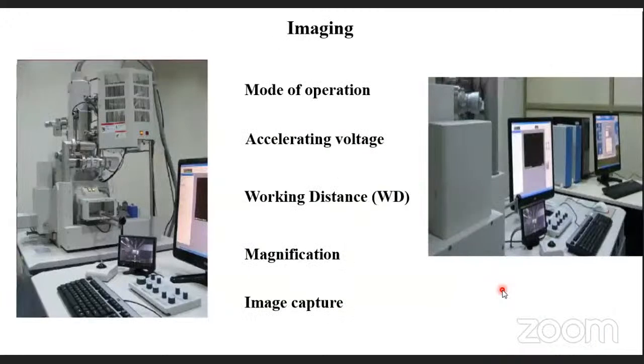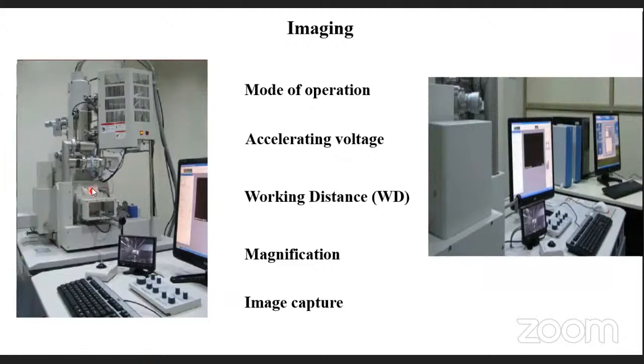After sample preparation, we come to the instrument and open the exchange chamber. We place the sample holder inside, push the sample in, close the chamber, and start the analysis. Before going for analysis, you should understand which mode you require — decided by you and the technical staff. We have different modes: secondary electron mode for basic analysis, and backscatter electron mode if you need elemental contrast.